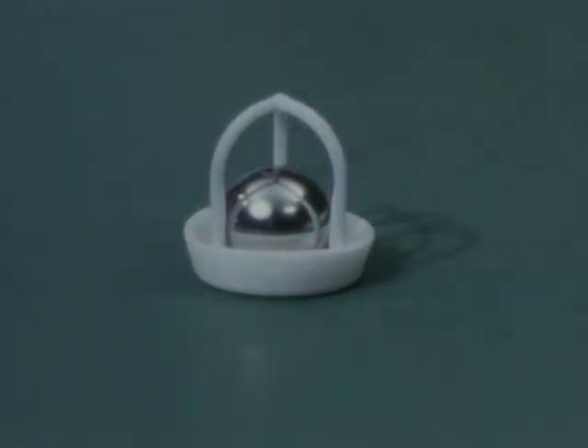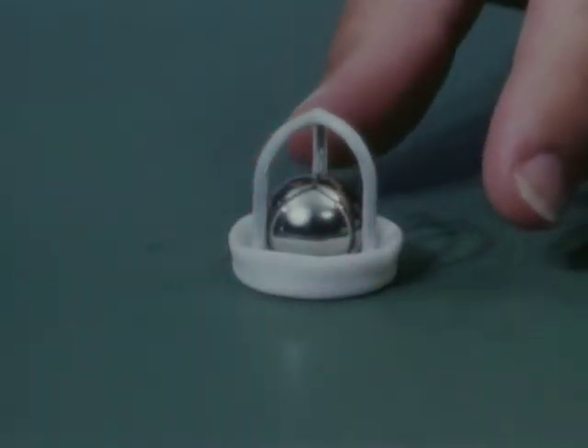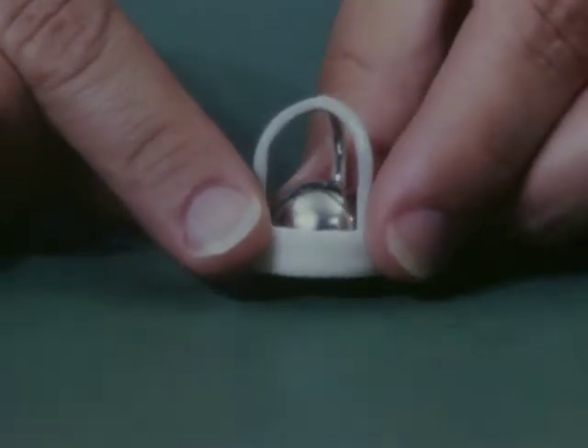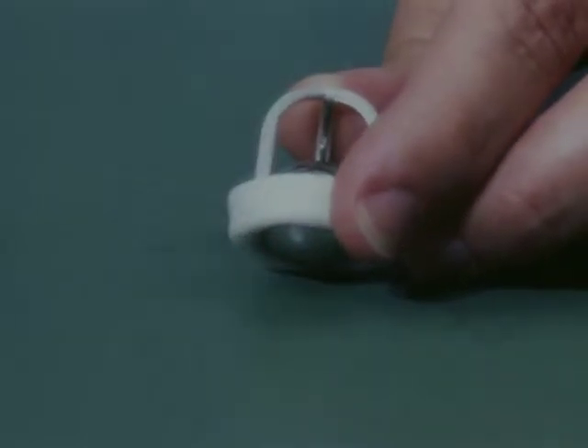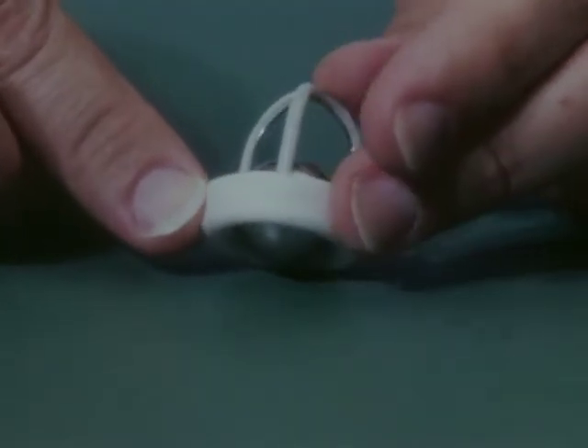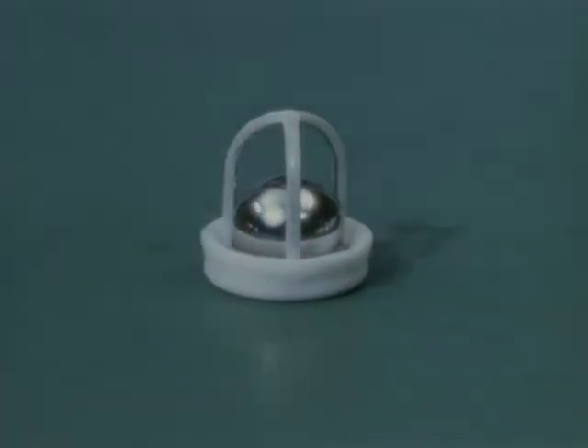Concern about the two-ply cloth undergoing wear and fragmentation has led Edwards Laboratory to introduce a new series — 2400 and 6400 — which features a thin inner metal track as the only part of the covered cage that contacts the ball. This model is in a developmental stage, and its major drawback is an excessive amount of noise.